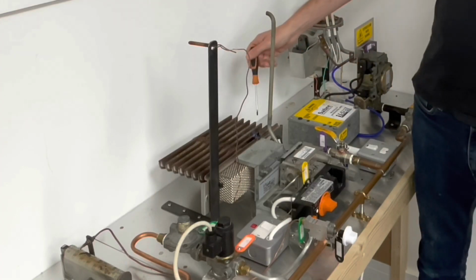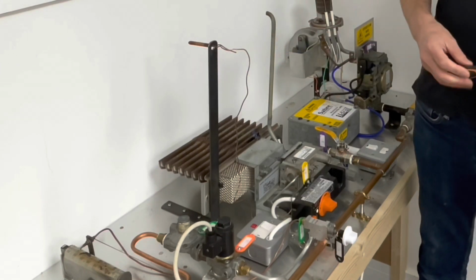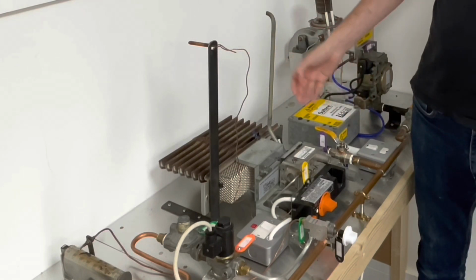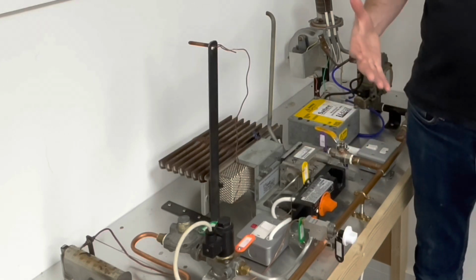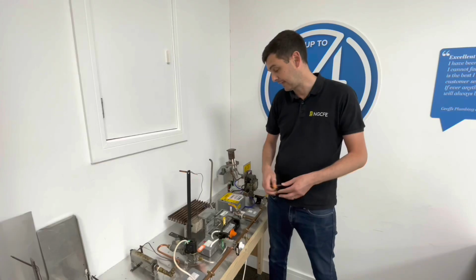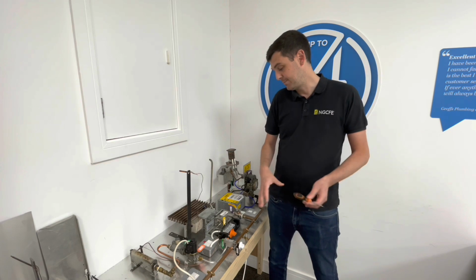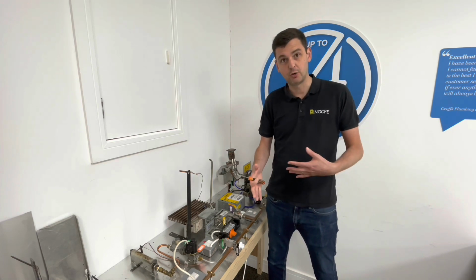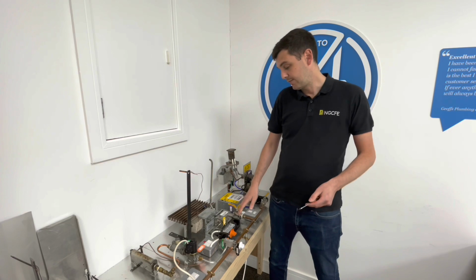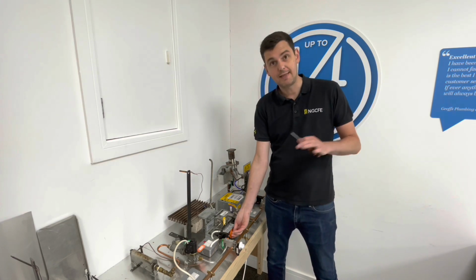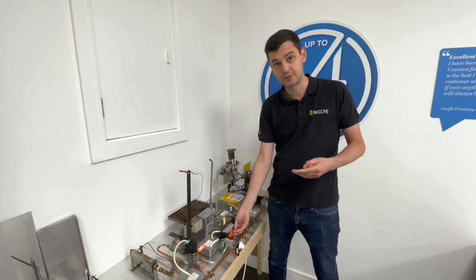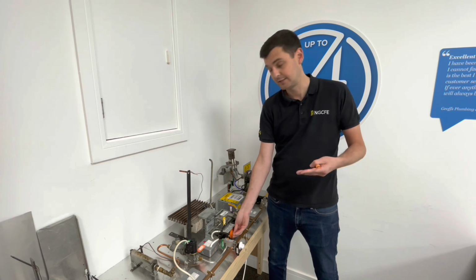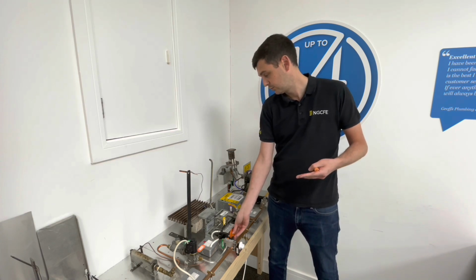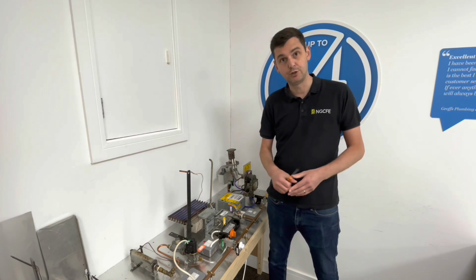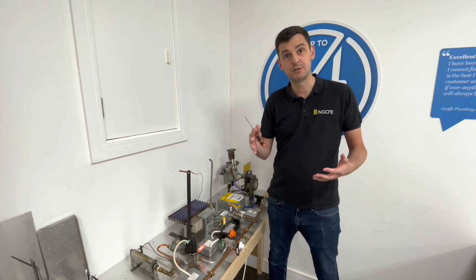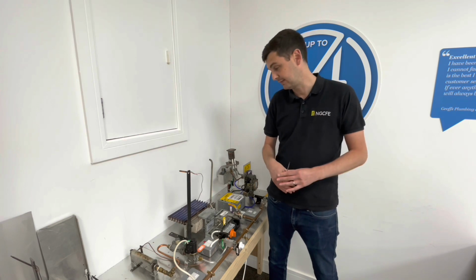So we can see here our pilot's lit. It's already lit, so our thermoelectric valve is energized. The valve's held open so that we're getting gas through to the pilot. The regulator we don't need to go into because we're not going to range rate it. However, if we now set the thermostat on the electric thermostat side to allow enough electricity through, we'll see our back boiler unit then lights. It allows gas through to the main burner by opening up the solenoid valve.